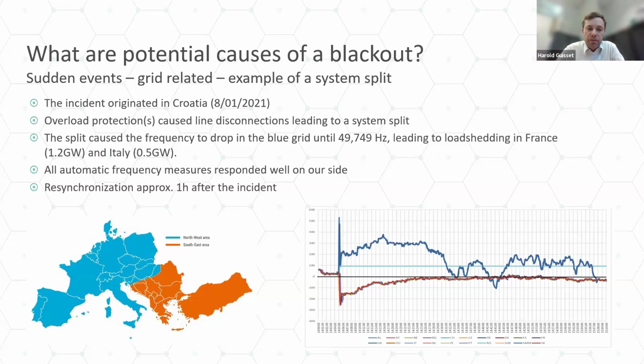Here we have an example of a system split where the European grid was separated in two big areas. It happened in 21. And the cause was an issue in a substation in Croatia. So you have to imagine that a problem in Croatia is causing load shedding in France and Italy. It really shows how interconnected the grid is. Basically, an issue in the substation caused failures in different substations along the blue-orange line that you see on the little map. And the flows of electricity in Europe were disturbed, and one area went into over frequency and the other area went into under frequency.